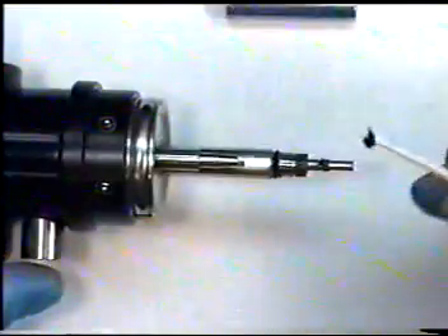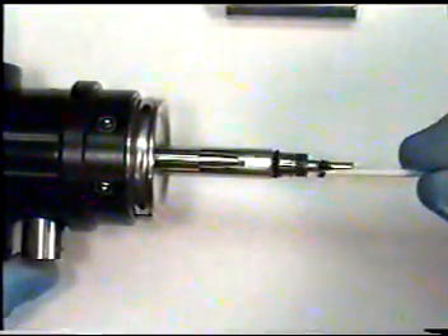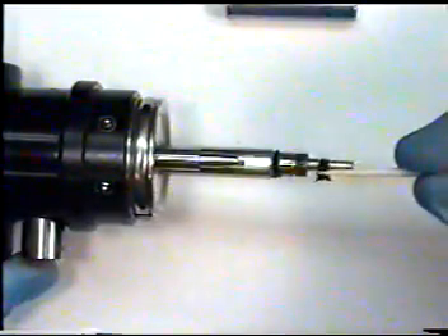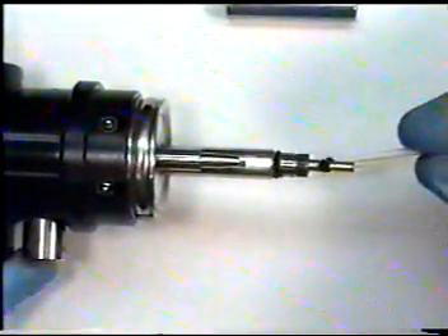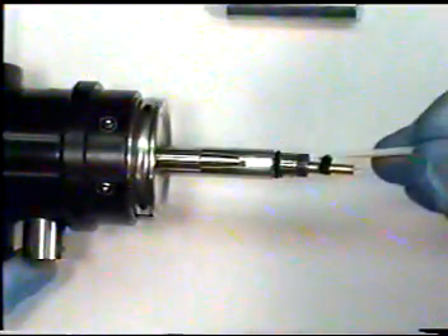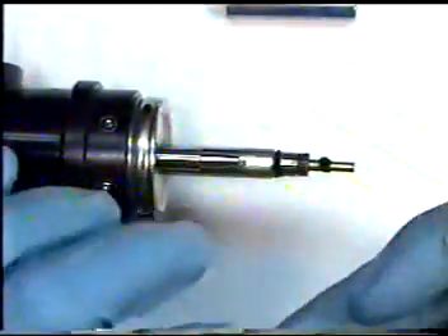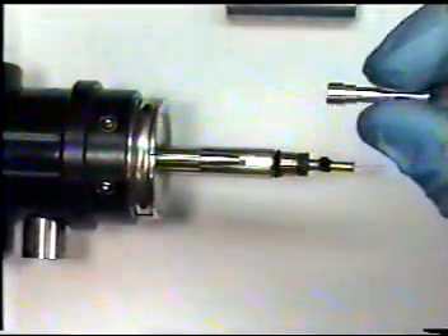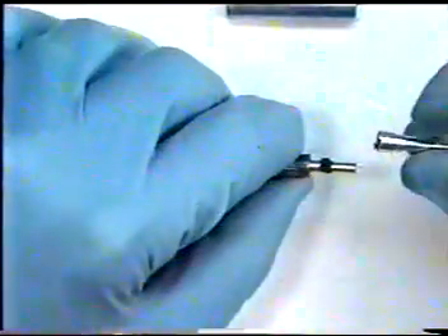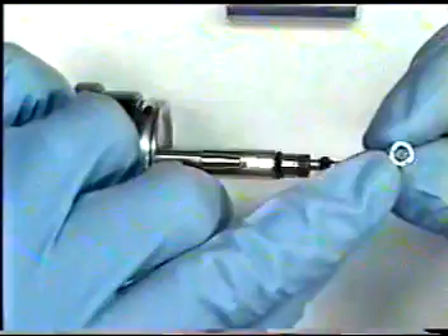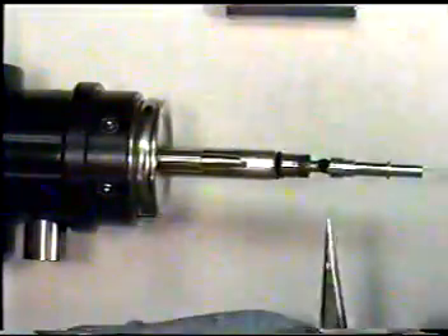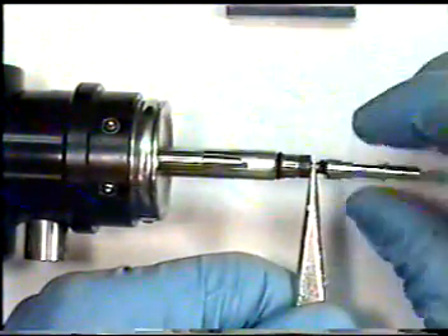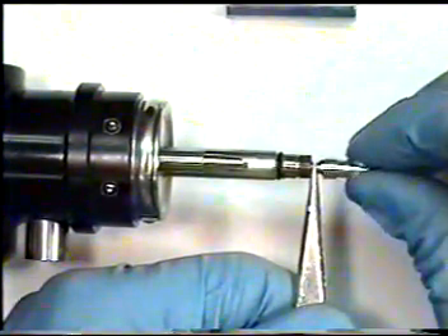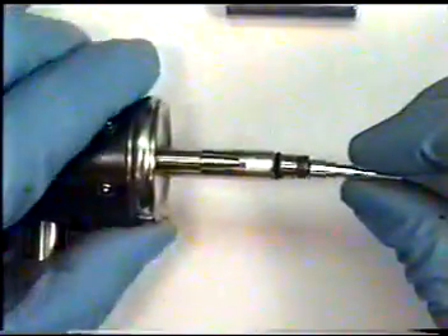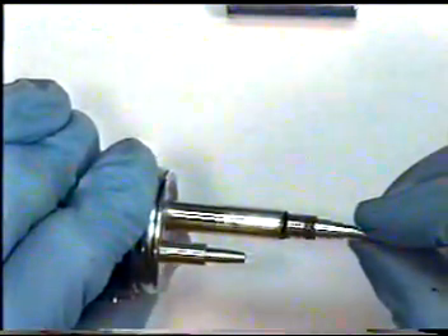Once the proximal end is fit through, use some black RTV sealant around the threads of your proximal fitting of your new light guide bundle. Put a thin coat around the threads. Retrieve the proximal end shaft, and as long as it is clean internally, slide over and screw on clockwise, holding it with a pair of tweezers. Do not let it spin within the shaft. Tighten down and slide the proximal fitting to fit inside the groove slot.